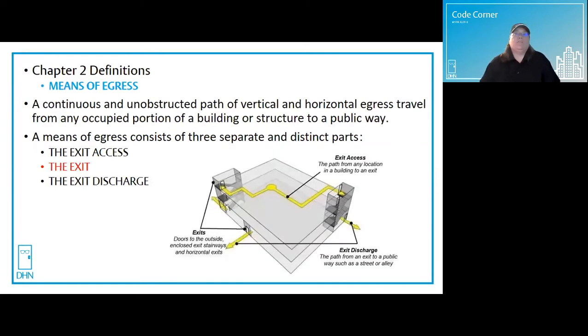I will be basing my answer using references from IBC 2015. Other editions are similar. Always consult your state and local code as well. In Chapter 2, the definition of means of egress is a continuous and unobstructed path of both vertical and horizontal egress travel from any occupied portion of a building or structure to a public way. A means of egress consists of three separate and distinct parts.